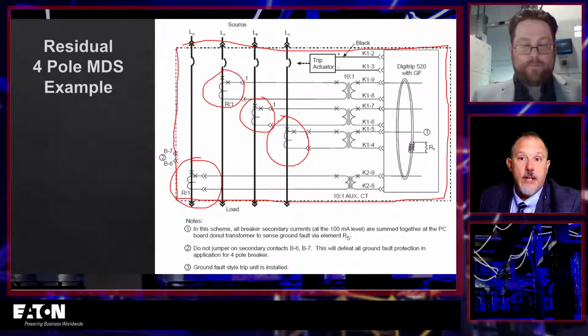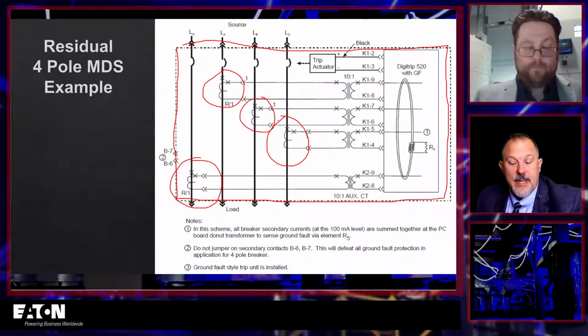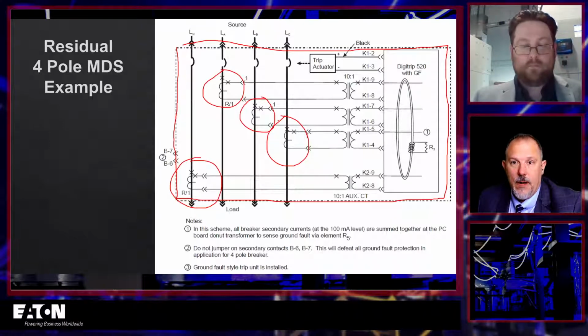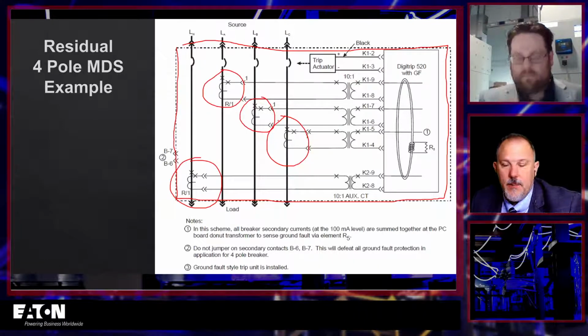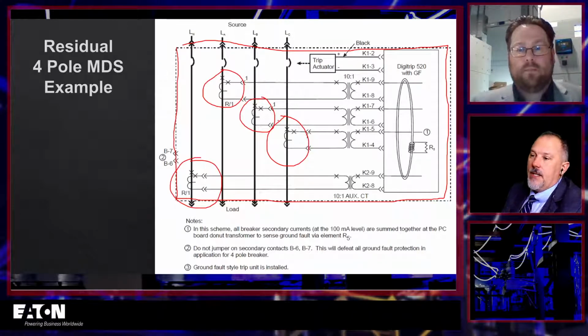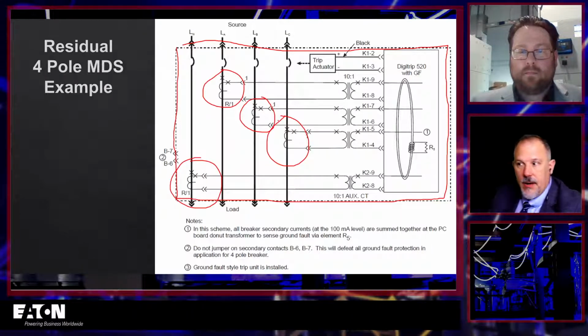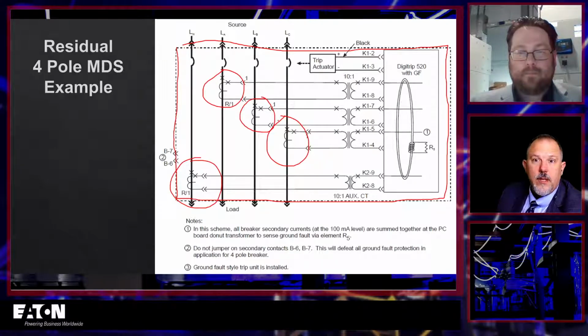This circuit breaker, you're not going to take it apart, right? It was tested at the factory. There's a test report that you can get with it. We tested the ground fault. We test everything on it. So if there's a miswiring, it's mounted to the bus. So I've heard people say, why would I test this for ground fault if it's a molded case circuit breaker? I know I'm doing basically the same test that was done at the factory. And true, you're not going to be testing the polarity, but you would be testing to make sure that the breaker wasn't damaged in shipment, wasn't damaged as it sat on the job site before it was actually installed, and all of those good things.